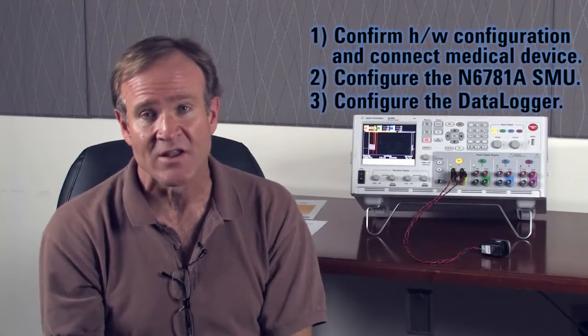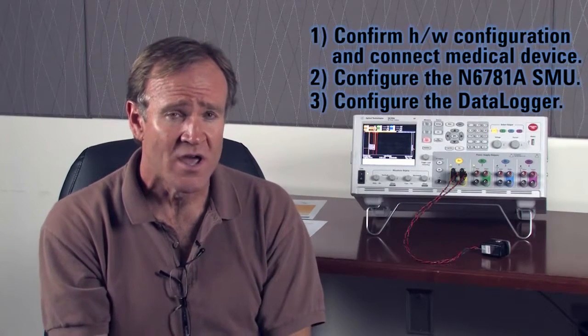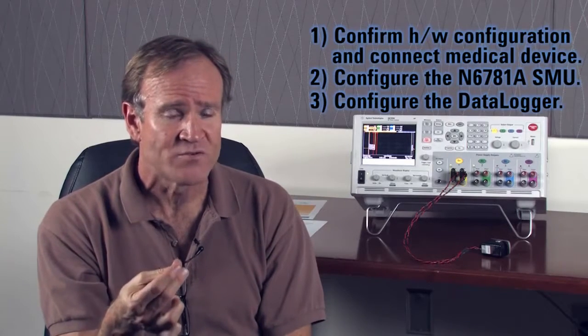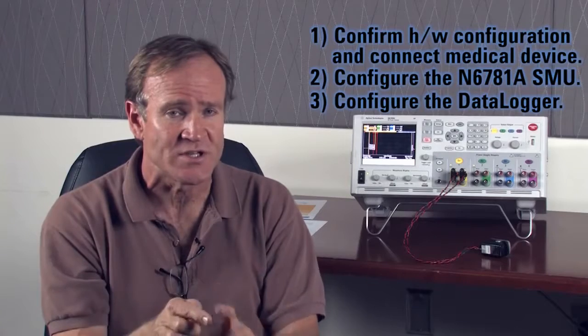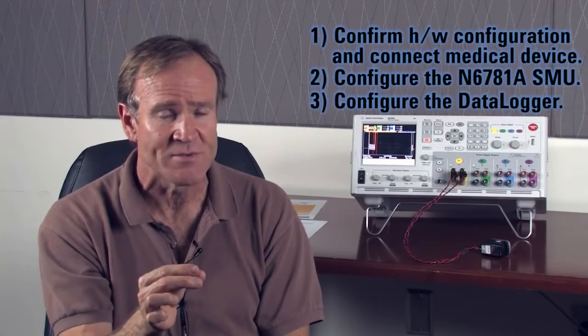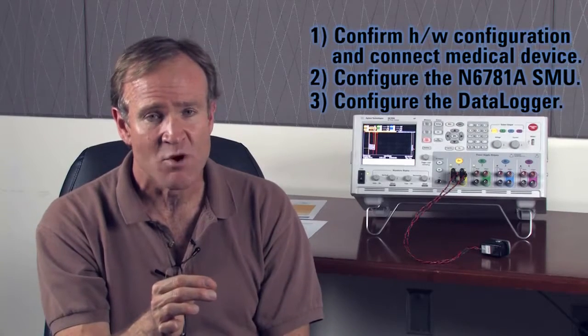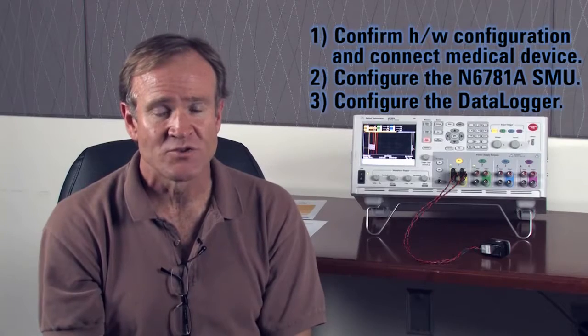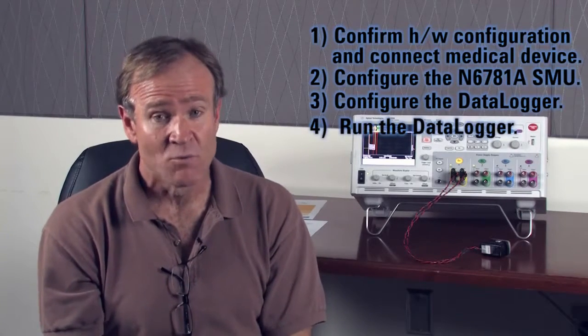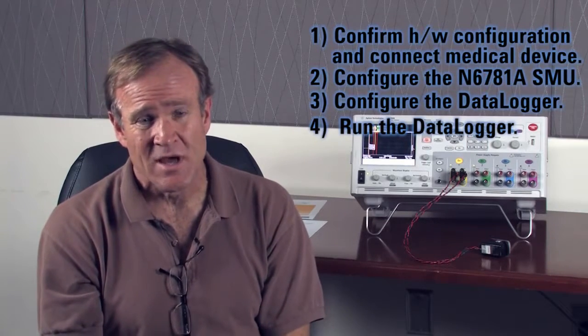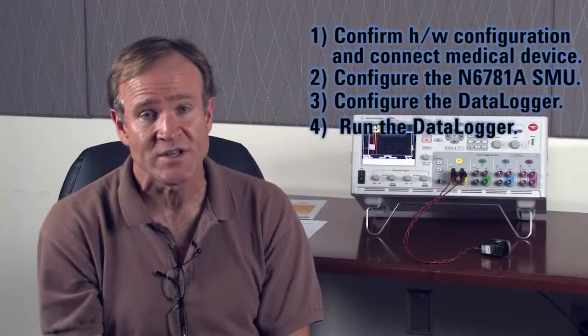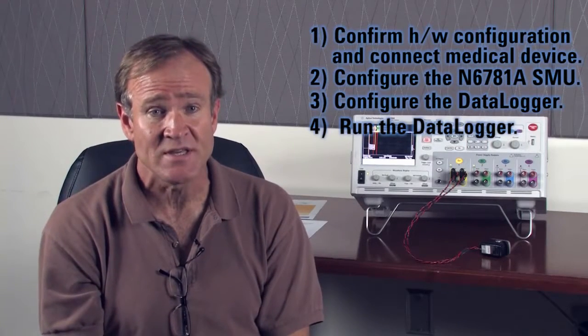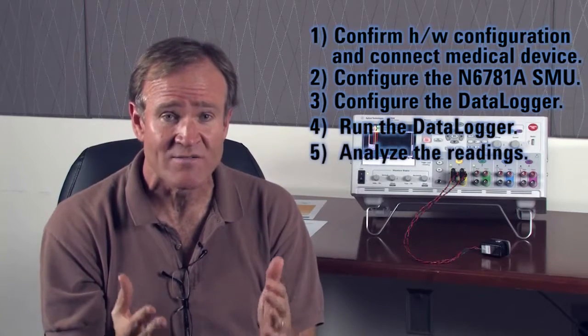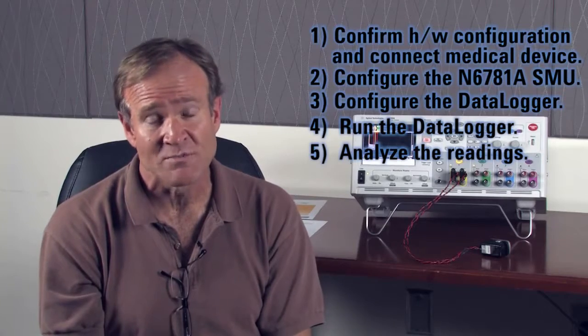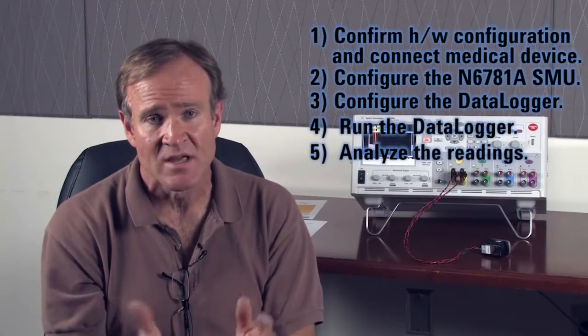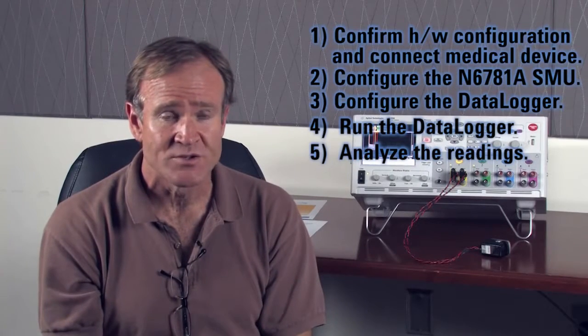Step 3, configuring the data logger. So when you're configuring the data logger, you're going to need to set that auto range for your current. You remember, this is what sets the seamless ranging. So setting that auto ranging is key to getting the measurement to work correctly. And then of course you want to set the appropriate time frame and sample rate that you're looking for. Step 4, you want to go ahead and run the data logger. Again, you're going to need to look to see what is the appropriate vertical and horizontal ranging so that you get a nice display of what you're expecting to see. And then finally, you turn on the markers, and step 5 is you analyze your waveform. And you can move those markers around to look at the peaks, the valleys, and get a good idea of what's going on as you're using your medical device.